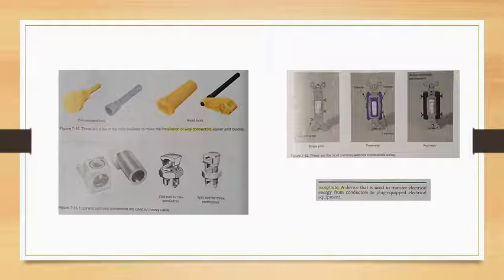Any circuit that is controlled from three or more positions uses a combination of three and four-way switches. The switch function, regardless of type, is to interrupt the hot, ungrounded wire only. The switch must never be placed on the grounded neutral or white wire or the grounding green wire. We will explore all types of circuits and how to connect them in section three of planning.